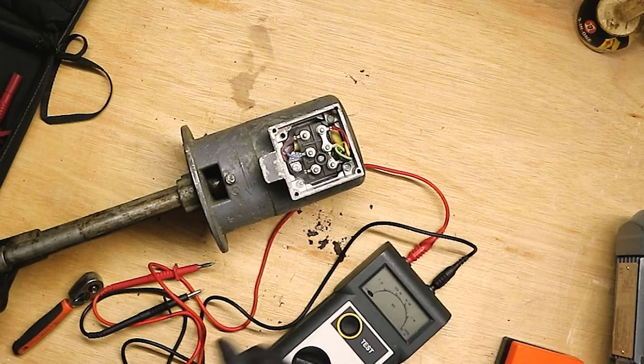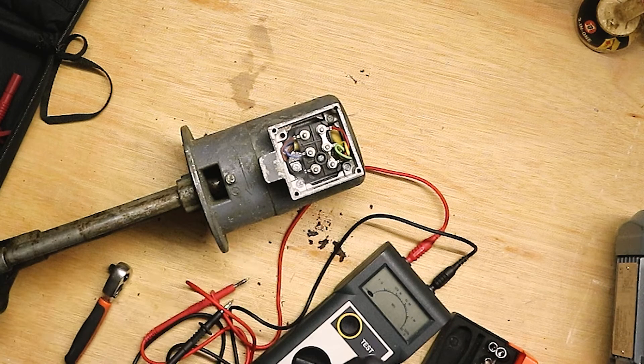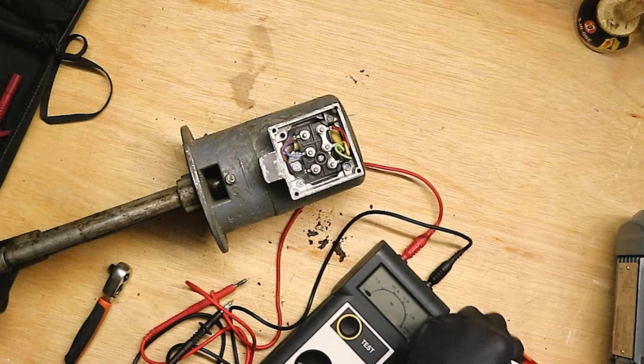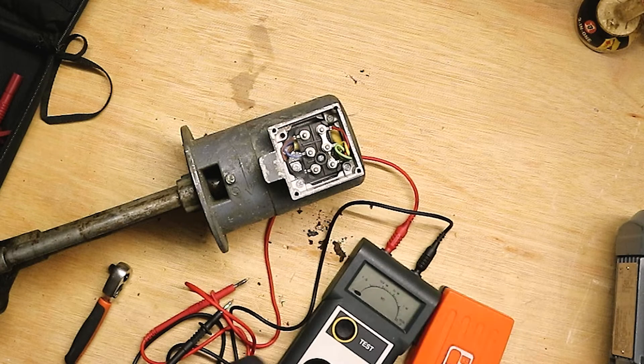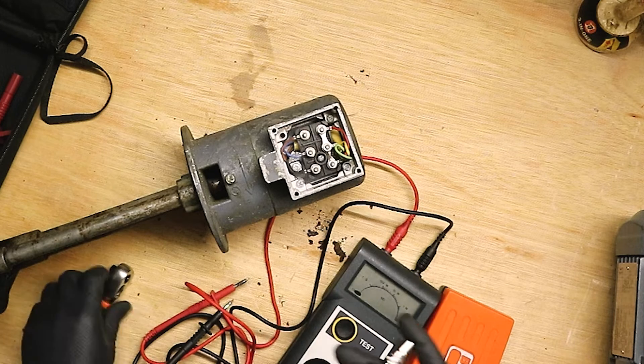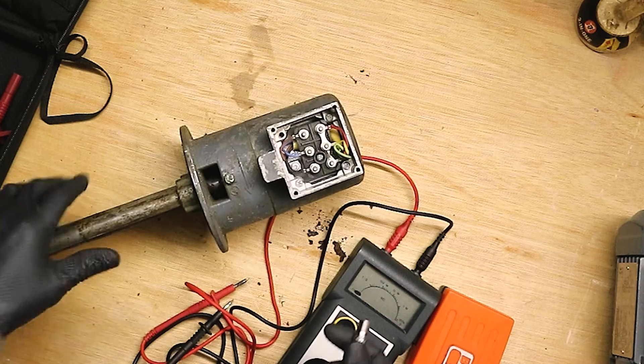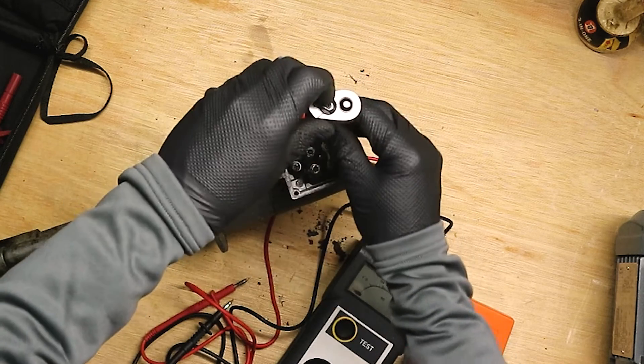So, it would be good to understand whether we've got an electrical problem or a mechanical one. Overload would go out either way, if it's got some sort of mechanical inhibition. And if the motor is stalled, then it will create an overcurrent.